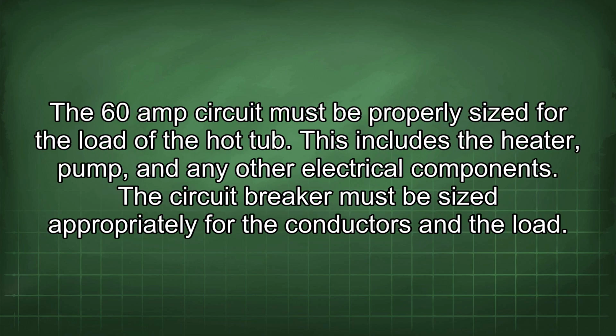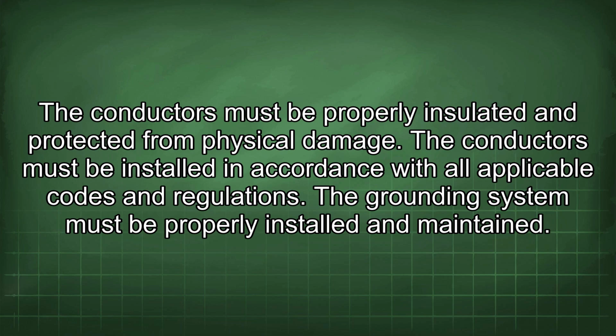The 60 amp circuit must be properly sized for the load of the hot tub. This includes the heater, pump, and any other electrical components. The circuit breaker must be sized appropriately for the conductors and the load. The conductors must be properly insulated and protected from physical damage. The conductors must be installed in accordance with all applicable codes and regulations.